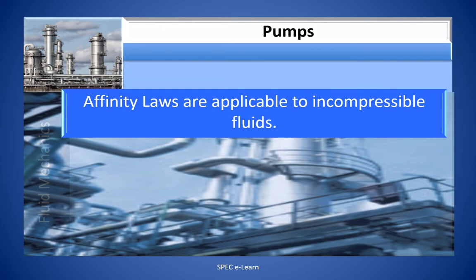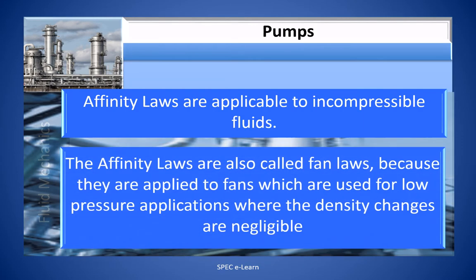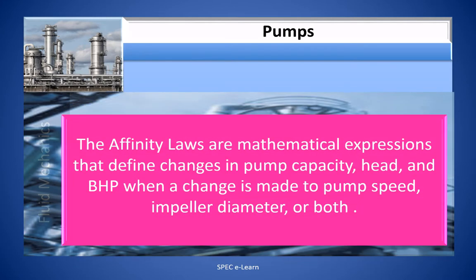Affinity laws are applicable to incompressible fluids. The affinity laws are also called fan laws because they are applied to fans which are used for low pressure applications where the density changes are negligible. The affinity laws are mathematical expressions that define changes in pump capacity, head, and BHP when a change is made to the pump speed, impeller diameter, or both.